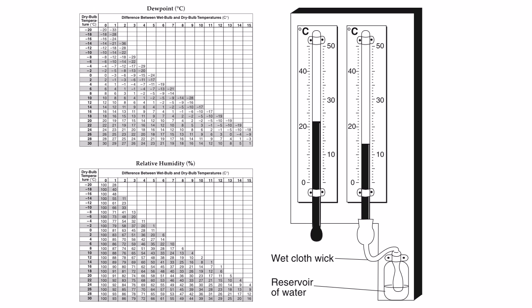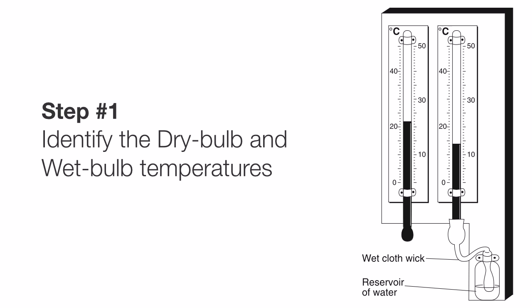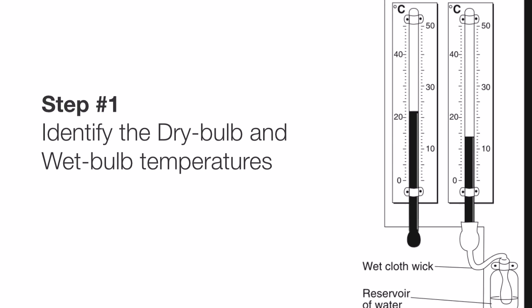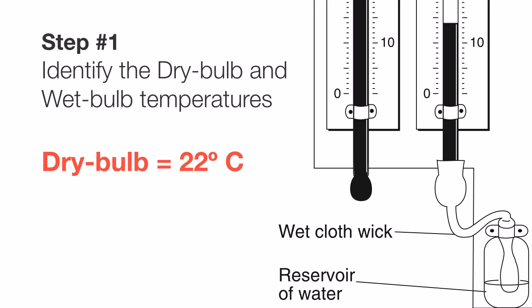So let's see how we use these tables. We'll begin by taking some measurements. Step one is going to be to identify the dry bulb and wet bulb temperatures according to your psychrometer. Let's use this one as an example. If you look right here, you'll see this is the dry bulb and the temperature appears to be 22 degrees Celsius. If we look over here at the wet bulb, we see the temperature appears to be about 14 degrees Celsius.